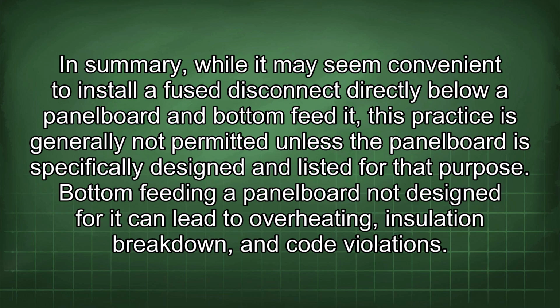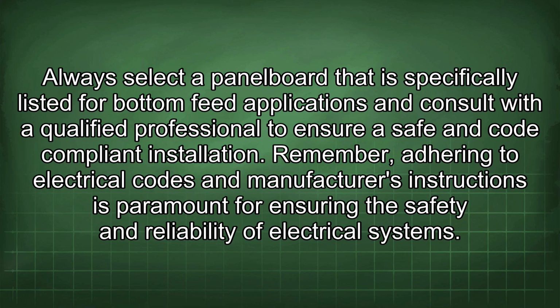In summary, while it may seem convenient to install a fuse disconnect directly below a panel board and bottom feed it, this practice is generally not permitted unless the panel board is specifically designed and listed for the purpose. Bottom feeding a panel board not designed for it can lead to overheating, insulation breakdown, and code violations. Always select a panel board that is specifically listed for bottom feed applications and consult with a qualified professional to ensure a safe and code-compliant installation. Remember, adhering to electrical codes and manufacturer's instructions is paramount for ensuring the safety and reliability of electrical systems.